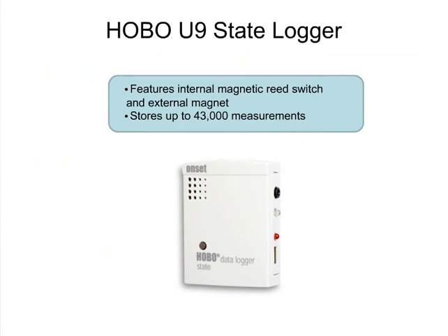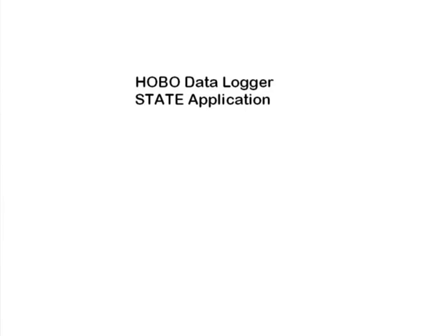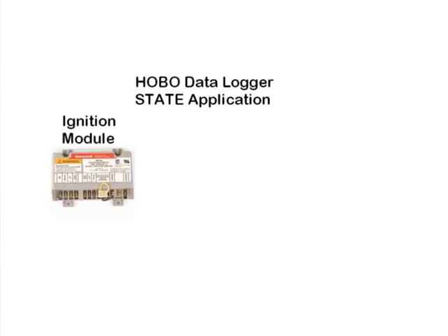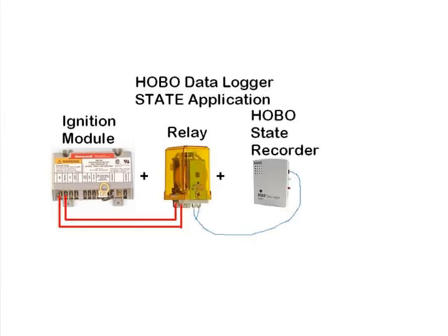In addition to temperature sensors, it is also necessary to monitor the operation of the gas valve, oil valve, or electrical contactor relay. We can perform this function with this wonderful little device known as a HOBO state recorder. It monitors a relay wired in parallel to the heat source valve, solenoid, or coil. When the heat source is on, the recorder logs the event with an on-time stamp. When the heat source turns off, the recorder again records a real-time stamp showing exactly when the burner or heat source shuts down, giving you an off-time stamp.